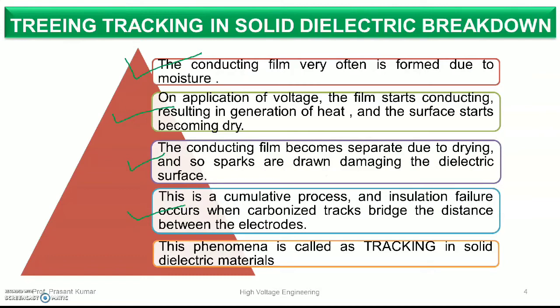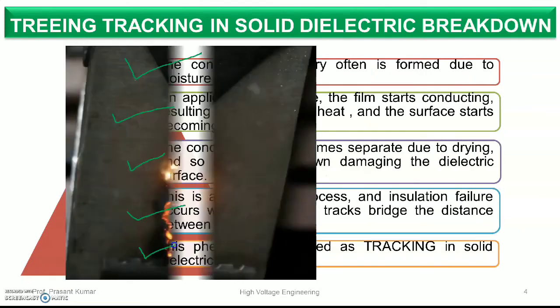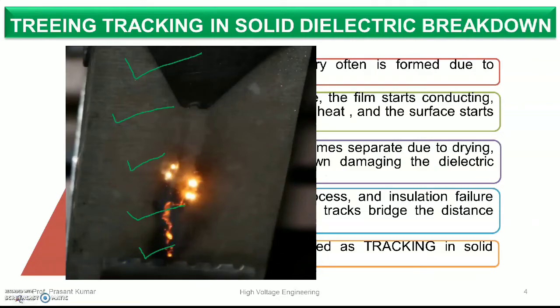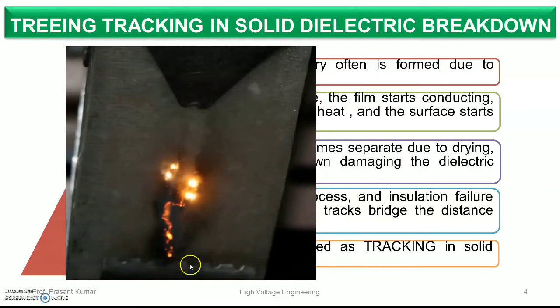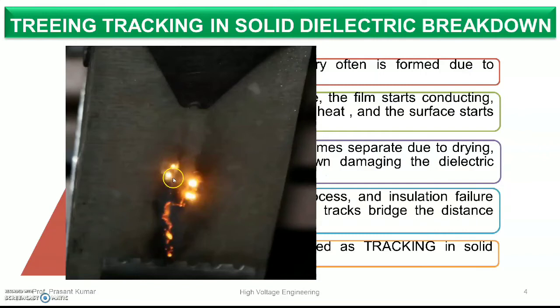The sparks are drawn, damaging the dielectric strength, and due to this, sparking and internal discharge occur in a cumulative process. Insulating failure occurs when the carbonized track bridges the distance between the electrodes. The internal discharge — that spark — is called treeing, and tracking is the process of tracing that path. The breakdown region forms like a tree shape on the surface.